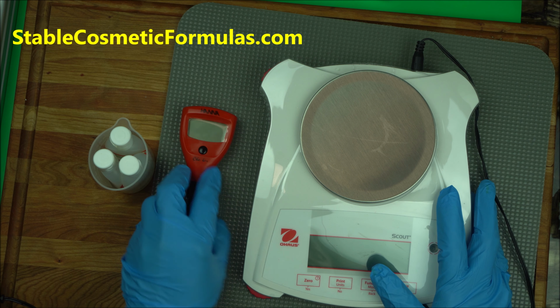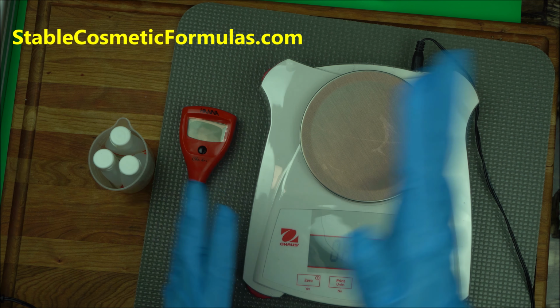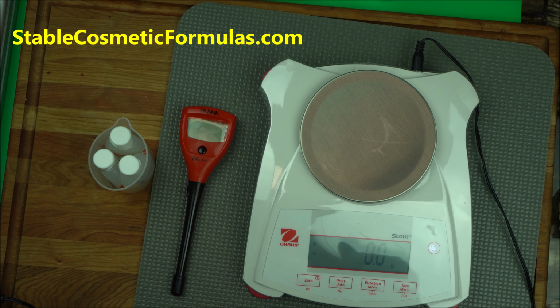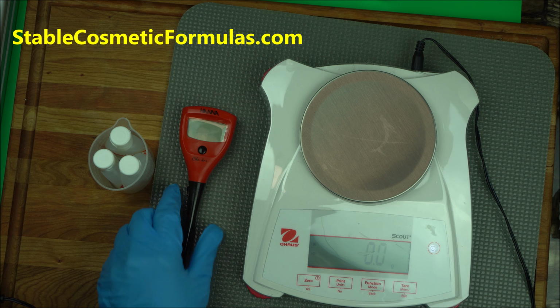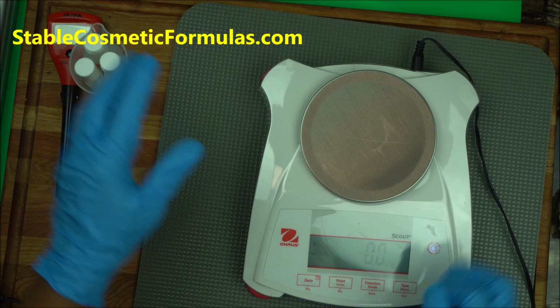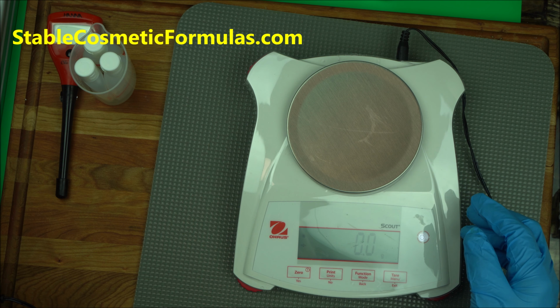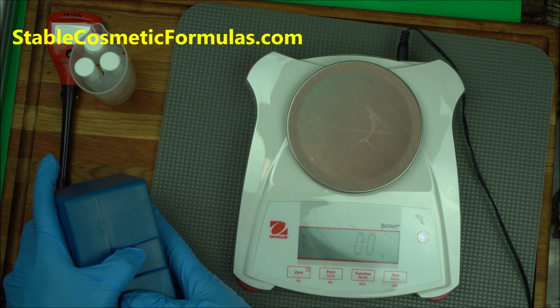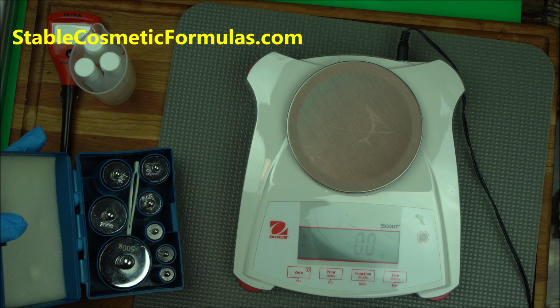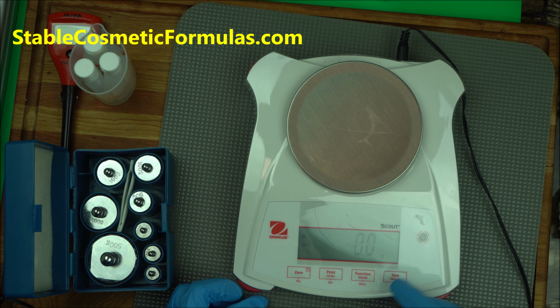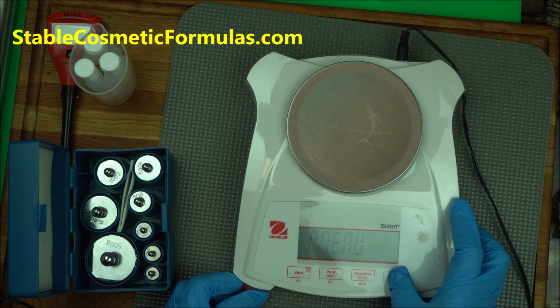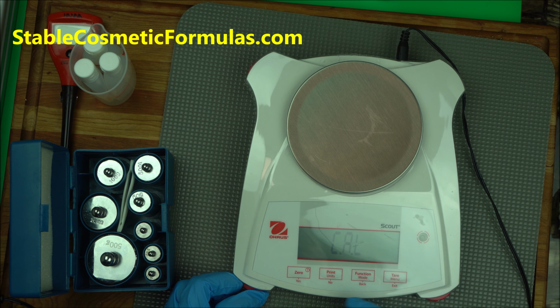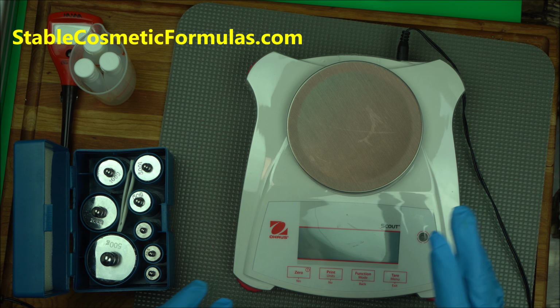So the first thing I do every morning is come to the lab, clean, make sure I sanitize my desk, make sure I have my gloves on, then we have to calibrate the scale. So the first thing, I calibrate my scale. So how do I calibrate my scale? If you have watched my video on this show, depending on the type of scale you have, different scales have different calibration procedures, right? So basically in my case, I just press the menu until calibration pops up. Then I'm going to click yes. I'm going to choose linear calibration. For me, it's the better one, it's the full calibration.